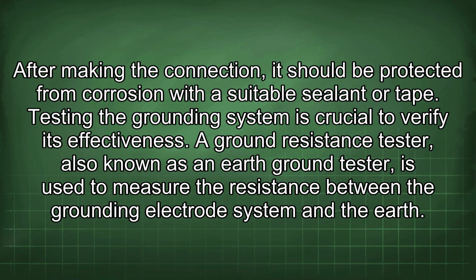Testing the grounding system is crucial to verify its effectiveness. A ground resistance tester, also known as an earth ground tester, is used to measure the resistance between the grounding electrode system and the earth.